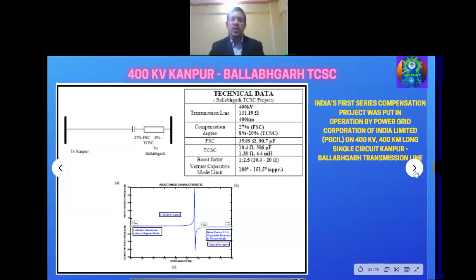And these are some of the technical details, like the 400 kV line. Its length is around 400 kilometer, having a resistance of 131.19 ohm. Then the compensation degree by fixed series capacitor is 27% compensated, and by TCSC it is compensated by 8 to 20%. Then the FSC resistance and capacitance are given, the TCSC resistance and capacitance which are connected, and also the reactance connected in that circuit. Then the boost factor and the Vernier capacitive mode limit are also given. So this is all about the Kanpur Ballabgarh thyristor controlled series capacitor FACTS device.